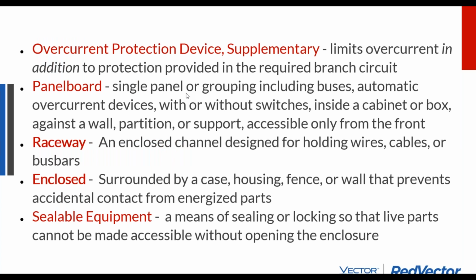Let's see. So a raceway is an enclosed channel designed for holding wires, cables, or bus bars. Enclosed is a standoff, but okay. But if I have a metal piece of unistrut that is open on one side, or a cage of wires, versus a fully enclosed conduit, what is the definition? A raceway, regardless of whether it's conduit or specialty cable, refers to that enclosure, whether it's fully or partially enclosed. The way the cable is making it from start to finish is through a raceway if it has any kind of enclosure at all. Some cables will be rated for use outside of conduit or outside of a raceway even, depending on how strong they are.